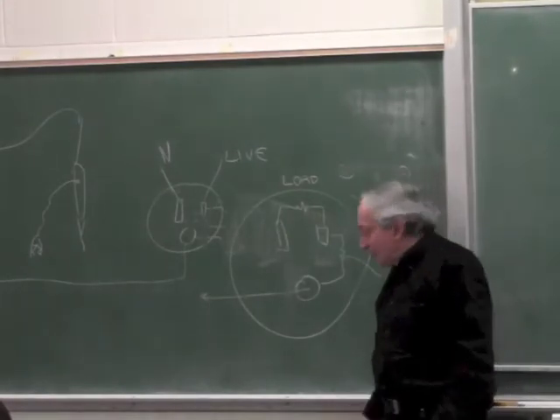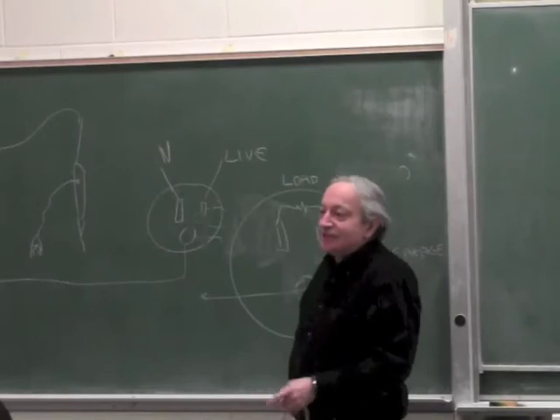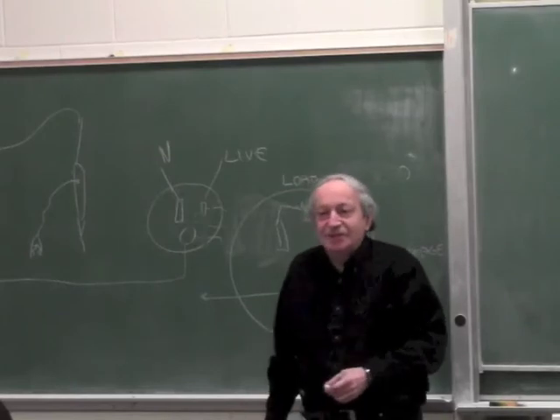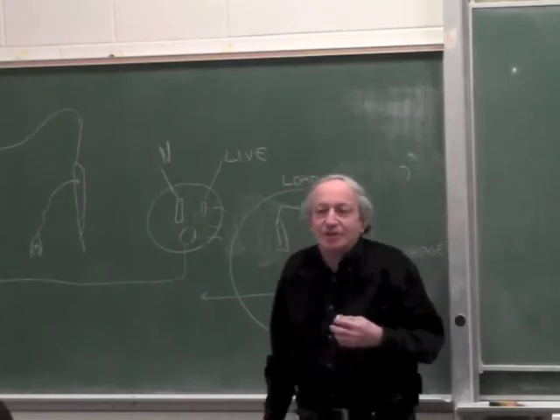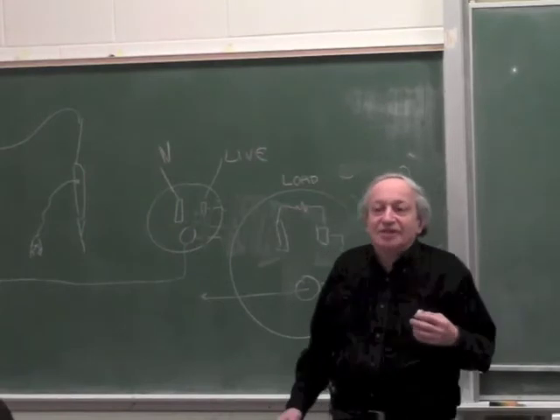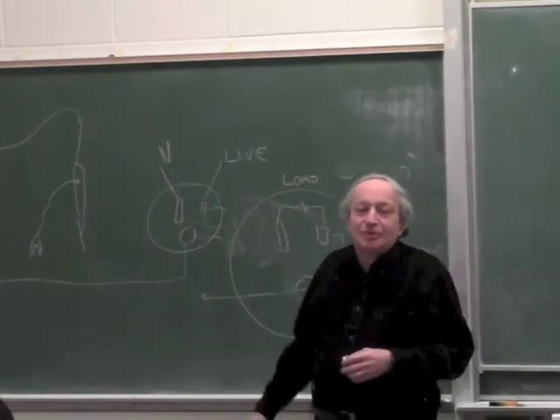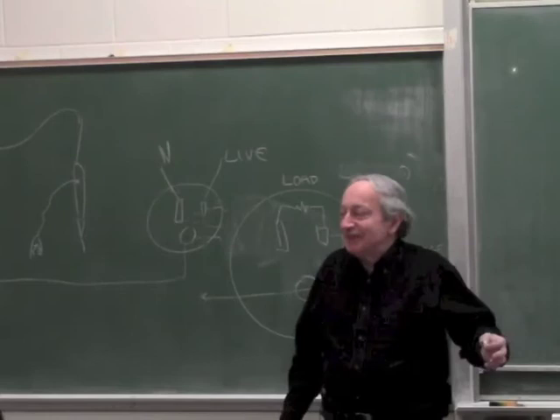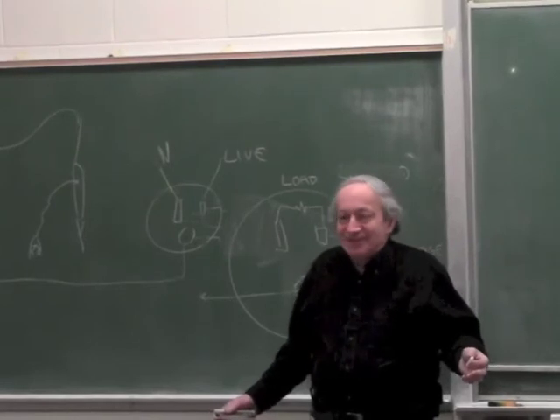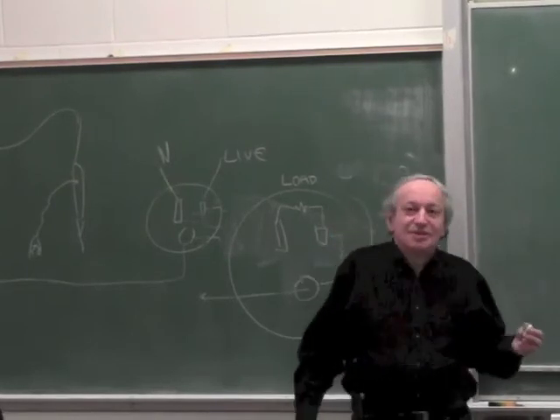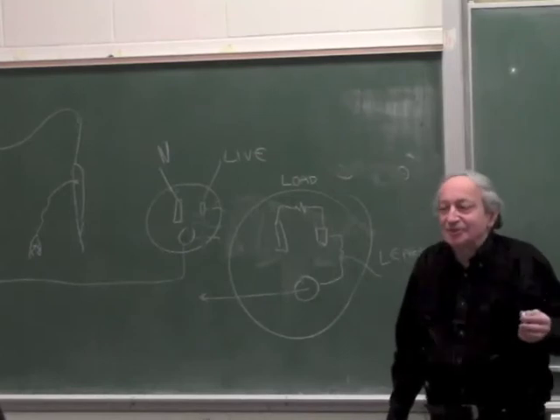So two grounds in two rooms are not really the same potential, and this creates ground loops. Our concern with ground loops is if we have a system with a sensor in one room and a controller in another room, the reference is not the same. In some systems it's a big problem, like in audio systems.